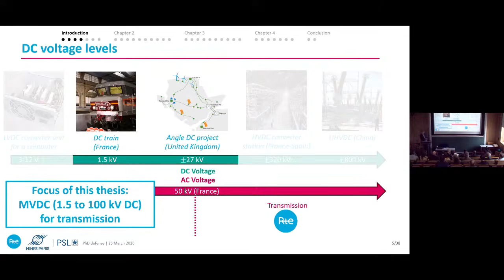I define MVDC in my thesis as 1.5 to 100 kilovolts DC. My thesis mostly concerns transmission systems. Since MVDC spans below and above 50 kilovolts, it's unclear whether it belongs to transmission or distribution, so I will focus on the application for transmission and RTE in the French case.